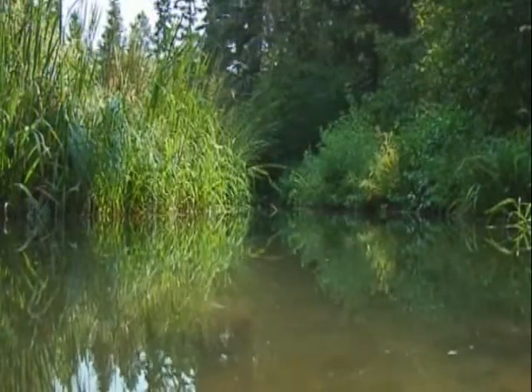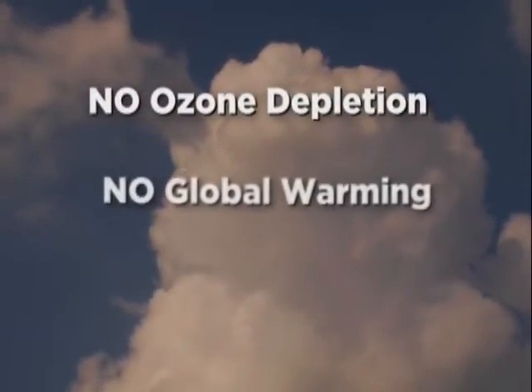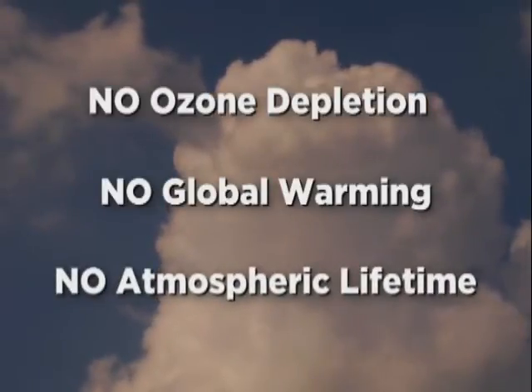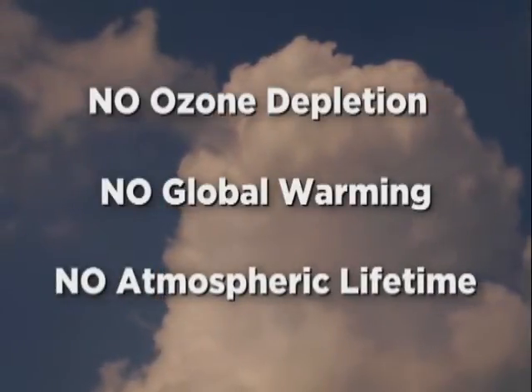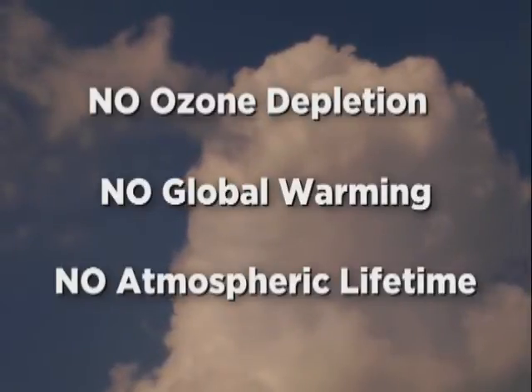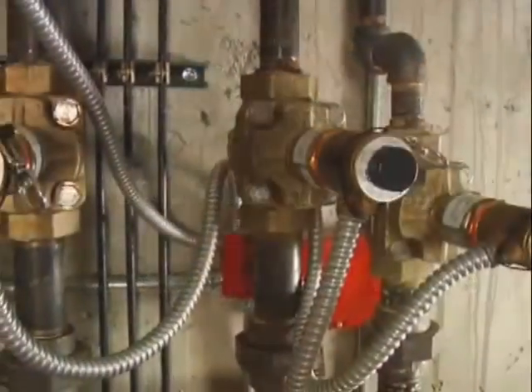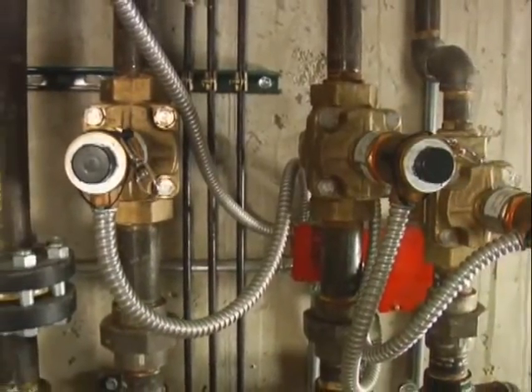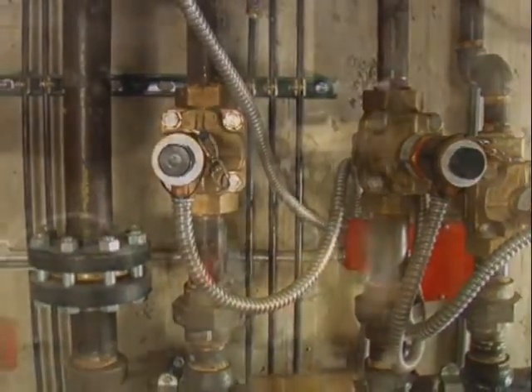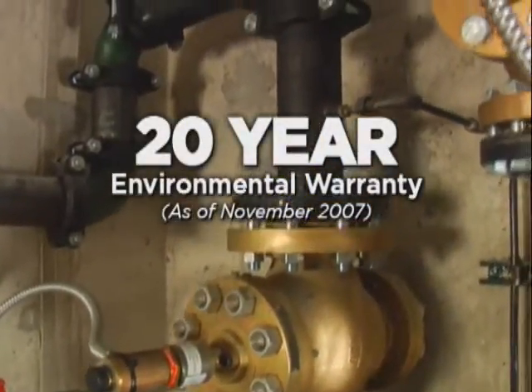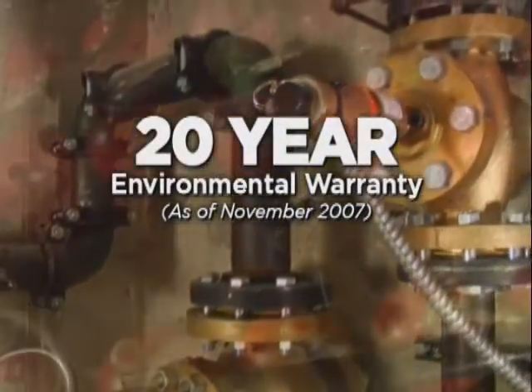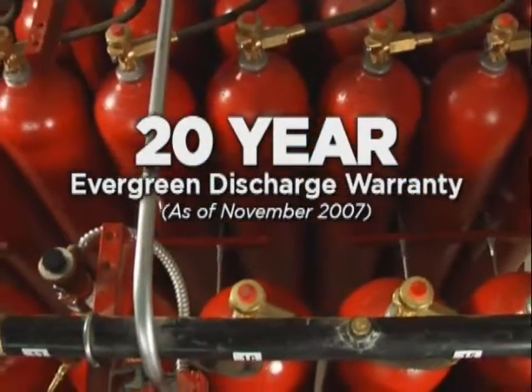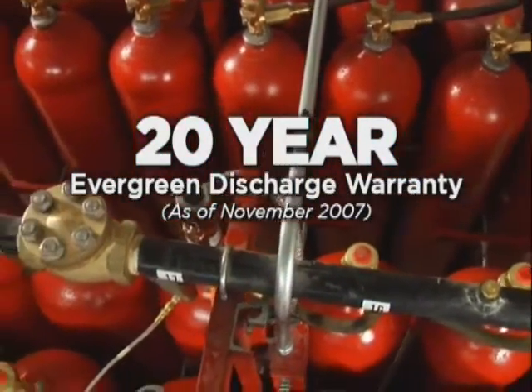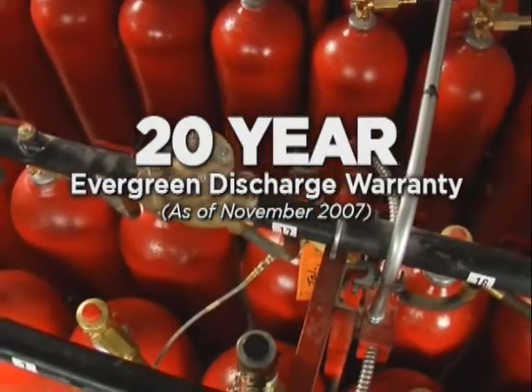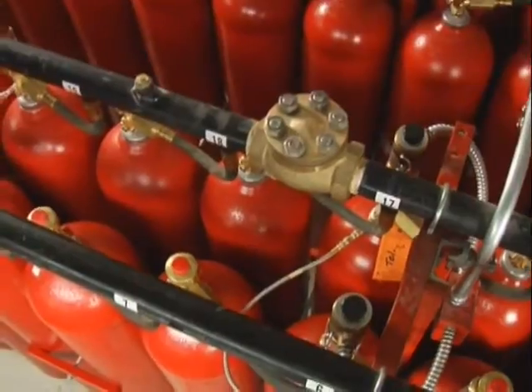In fact, the Inergen environmental warranty ensures that the agent does not contribute to issues of ozone depletion, global warming, or extended atmospheric lifetimes that could lead to the banning of Inergen. If Inergen is ever environmentally regulated due to one of those listed reasons, Ansul will replace the entire suppression system with a new clean agent system that complies with the new environmental regulations excluding water systems. And with the Evergreen discharge warranty, the Inergen agent will be replaced for free regardless of the cause of the fire suppression system discharge. How does Inergen work?